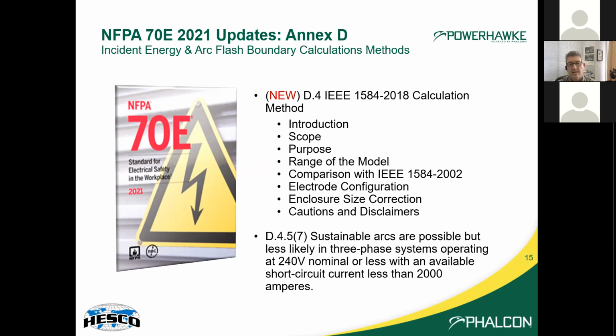The difficulty is it's not possible to know when scoping a project where you're going to have a short circuit current of less than 2000 amperes in your system. So we're working on a way to properly identify how to scope the analysis down to a certain spot in the electrical system, do some analysis, and then keep moving forward with more analysis if needed. The problem is, the further you go into the system, the more data has to be collected, and the more expensive it gets.